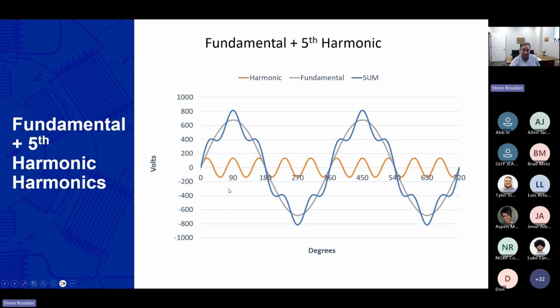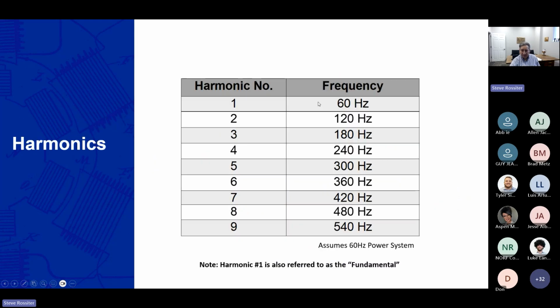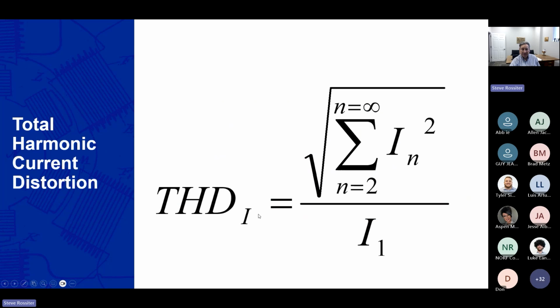So as we simplify these harmonics, which you have a range of these, we usually look at them up to the 50th harmonic, but really there's not too much that causes us problems through about half of that. And to get a term that you might have heard of, total harmonic distortion, it's simply the summation of the square of each of those harmonic currents and the square root of that over the fundamental 60 hertz. That comes up with a percentage that is harmonic distortion. It might have 20% harmonic distortion, current or amperage harmonic distortion, or 100%, or whatever that number is. That means something as we add up all of those harmonics and now quantify what that is.